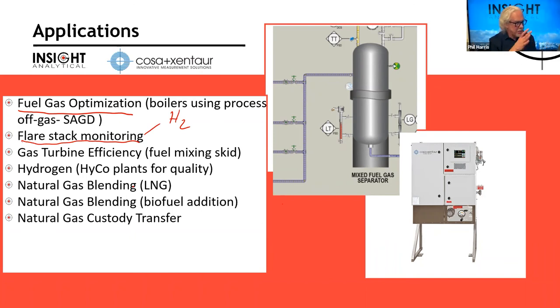But these types of analyzers, if it's really stable, if it's always high, like a place that's actually got a hydrogen plant that they're creating and they're using that hydrogen for fuel, if it's like 90% hydrogen most of the time, if it doesn't vary, then that's fine. We just take it out with calibration.